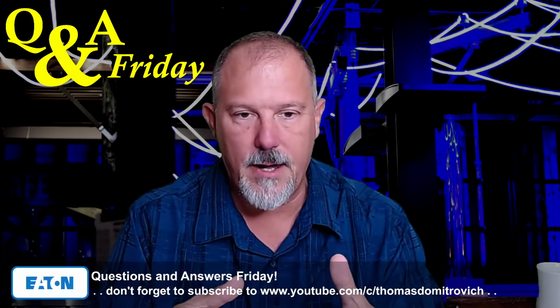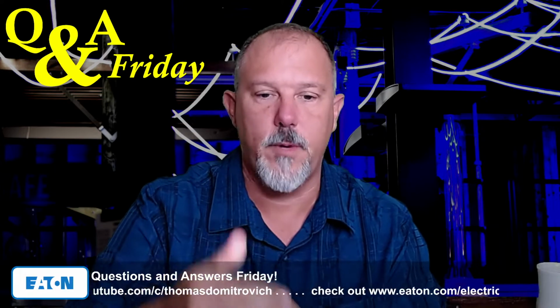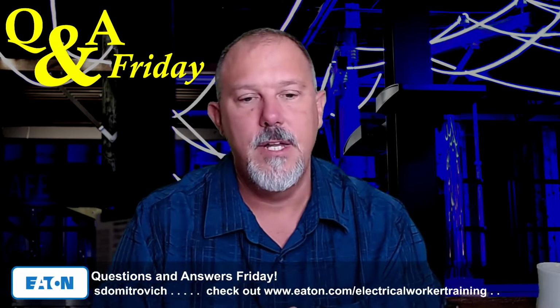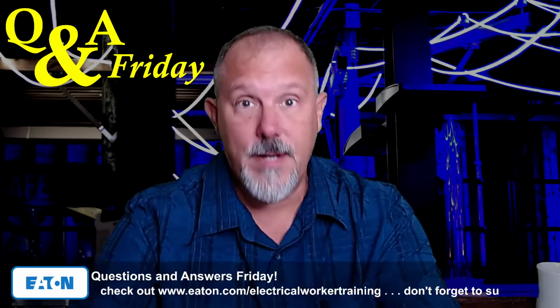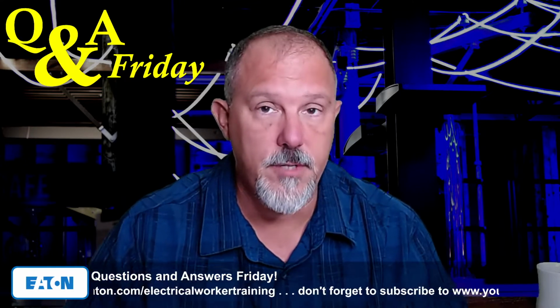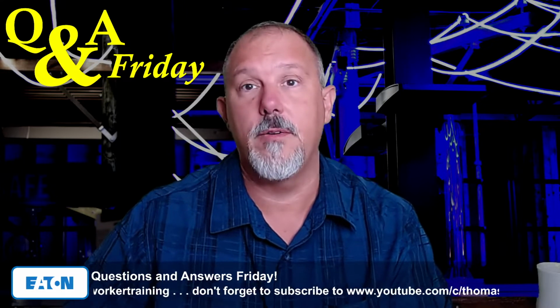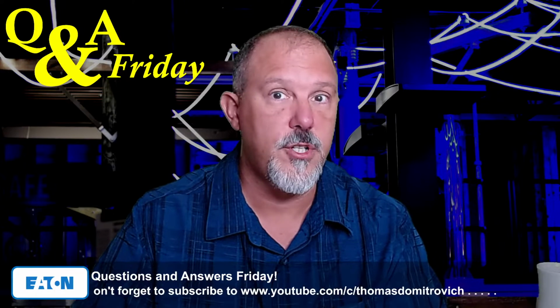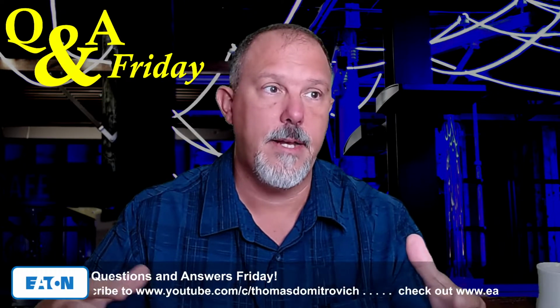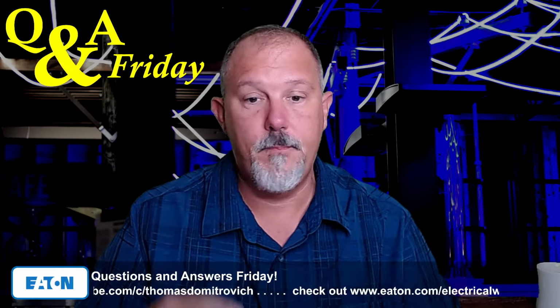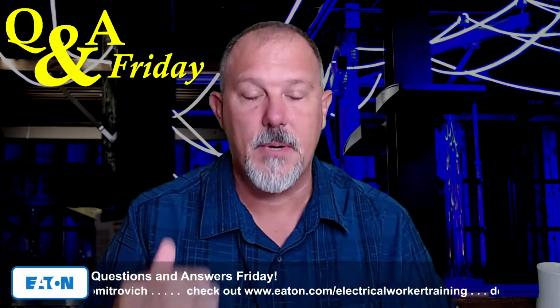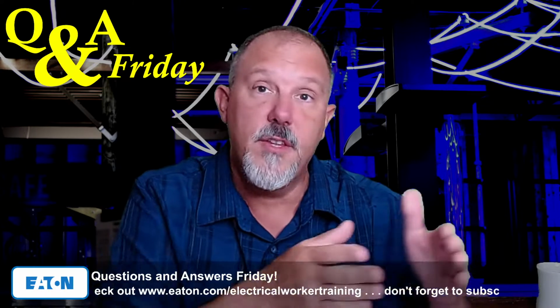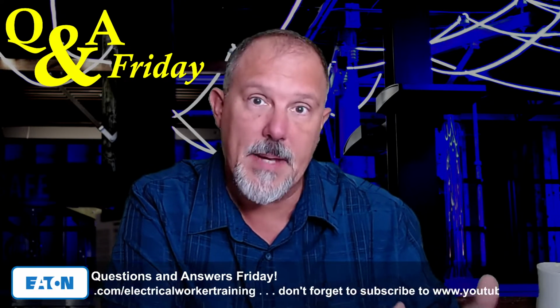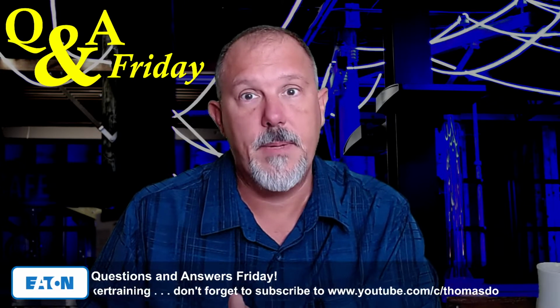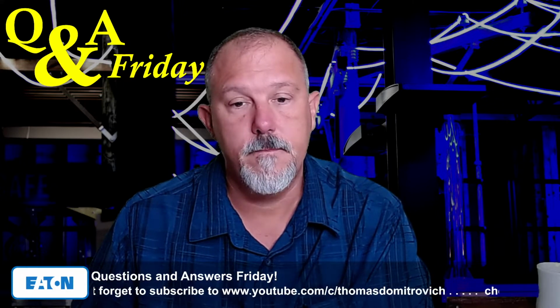So I agree with your point, JW. You pointed out that the utilities have much more rigorous employee training and equipment inspection and maintenance of their gear. I would emphasize the training more so than the maintenance. I believe they would do maintenance, but every facility should be doing maintenance on their equipment in its entirety, regardless of the voltage level, medium voltage or low voltage, and that's critical for 70E. But the training, the qualified person, is really critical. And in my opinion, the NESC may have requirements that anticipate that qualified person being there, which you can't anticipate on the commercial side of the business. That's just my opinion.